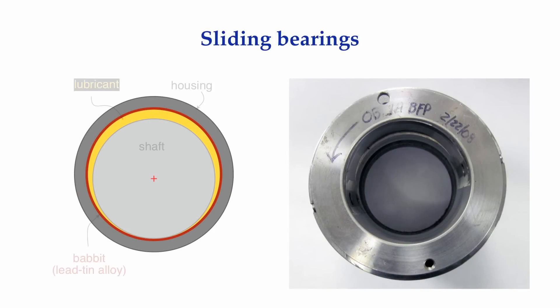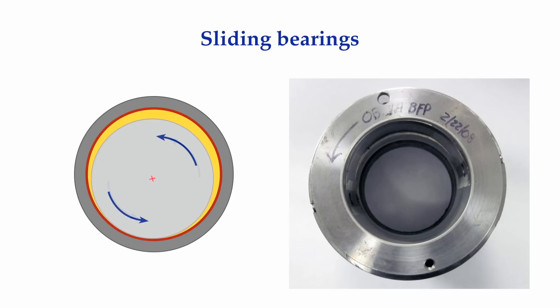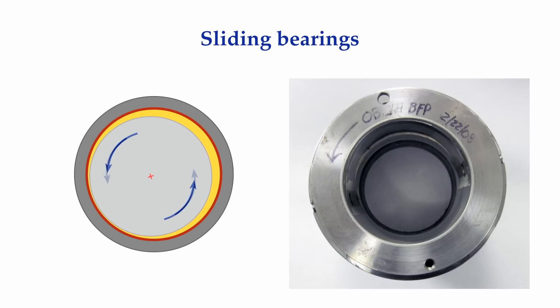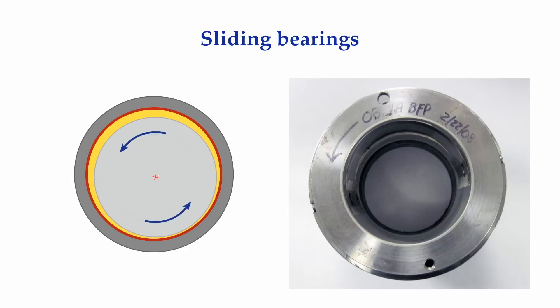There are two types of bearings typically used in rotating machinery: sliding bearings and rolling element bearings. The oldest bearing known to man is a sliding type bearing. In its simplest form, a rotating shaft is supported in a hollow cylinder, riding on a thin film of lubricant. As the shaft rotates, a wedge of oil forms between the shaft and bearing, lifting the shaft upward. Once the oil wedge is formed, the shaft typically moves to one side and does not run in the exact center of the bearing. This oscillatory shaft motion is what we refer to as vibration.